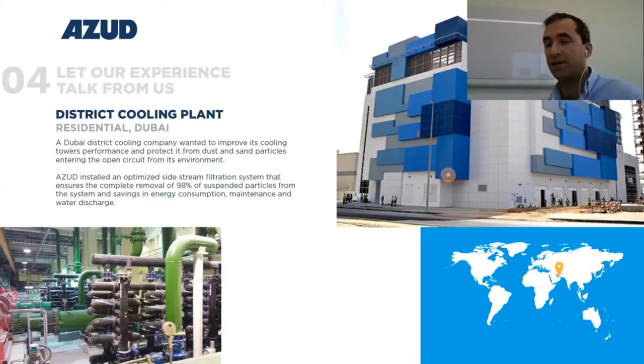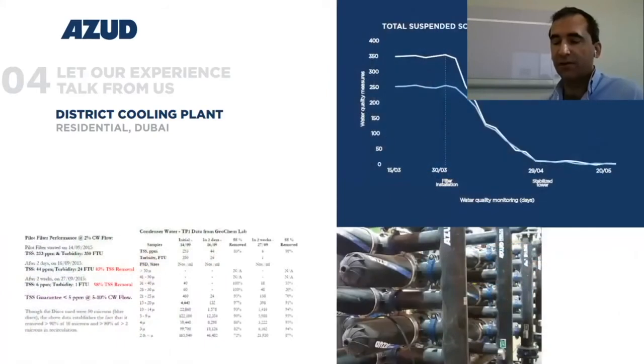So we installed a disk filtration Sidestream system, and we decided to monitor the water quality with a turbidity meter. Before the installation of the disk filter, the value was up to 350 NTU, and only after 20 days of the disk filter working, turbidity went down dramatically to 10 NTU. So we obtained removal of more than 90% of the TSS in the tower. So sandstorms were no longer a problem.